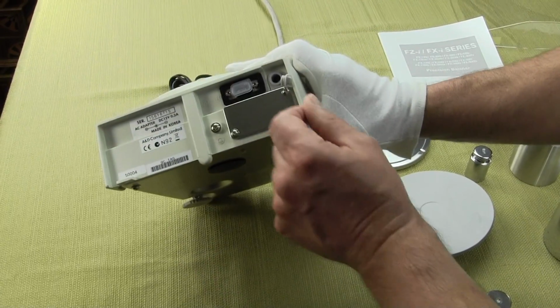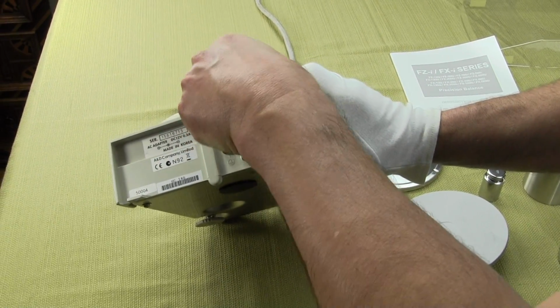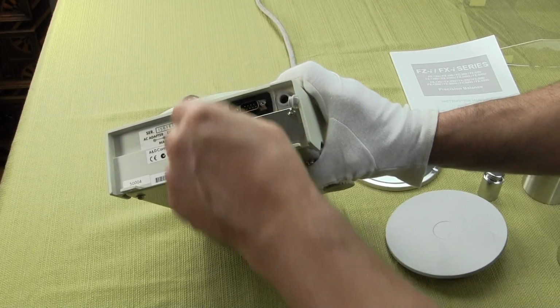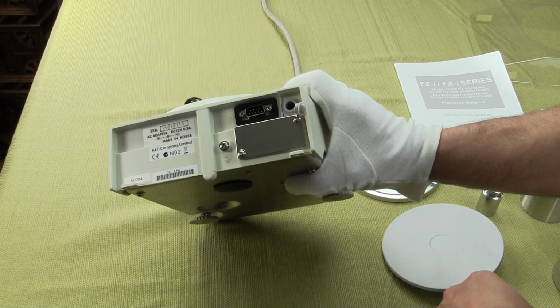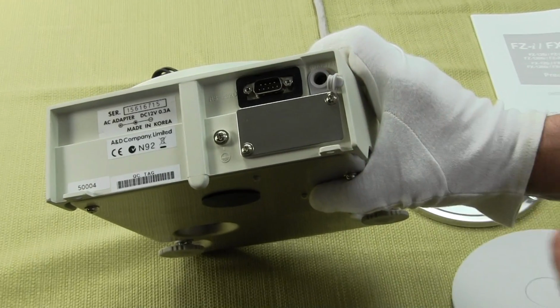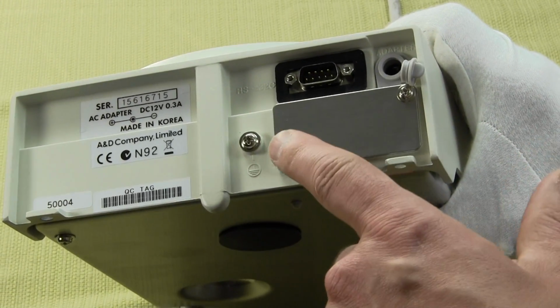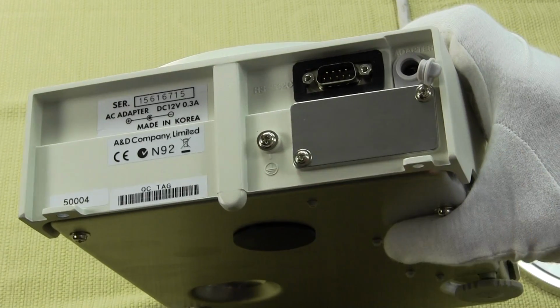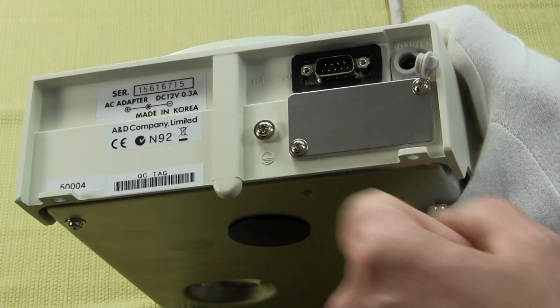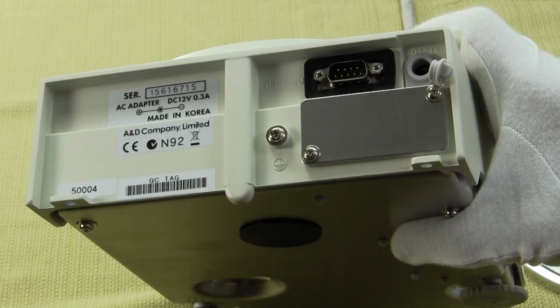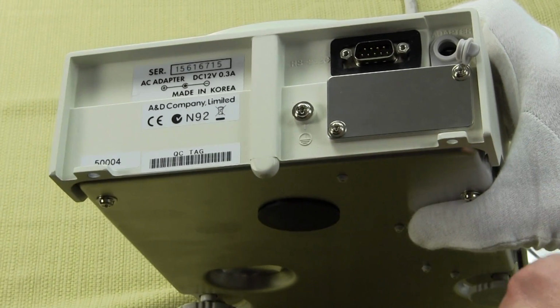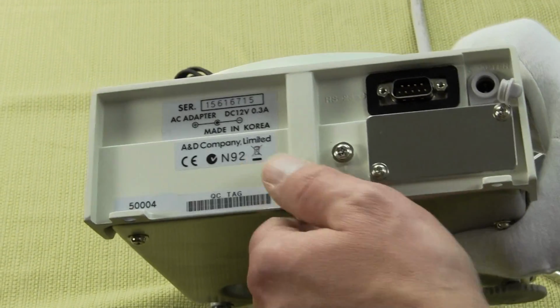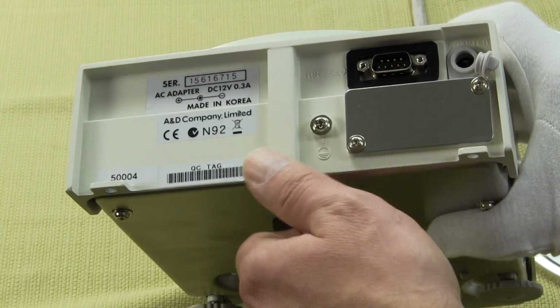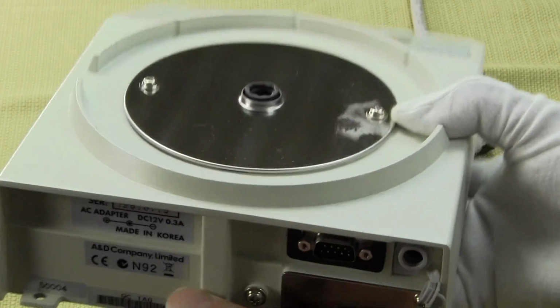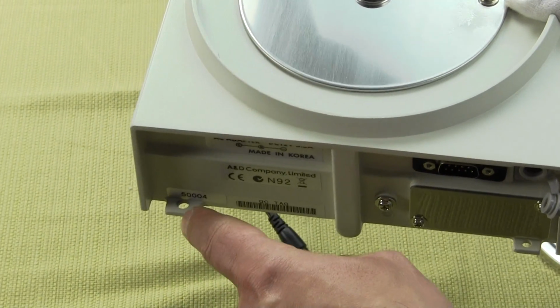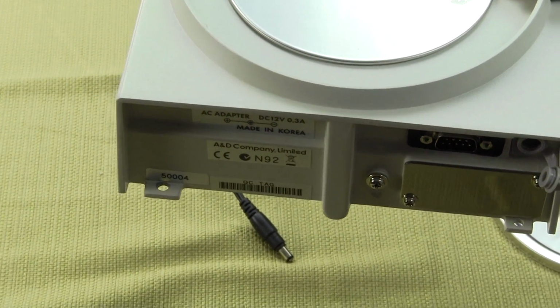On the rear of the balance, you'll see you have an RS-232 interface. So you have a 9-pin RS-232 interface. This would be used with a printer or if you're sending data to a PC. And then right under here, this is the port. And on this port here, if you open this up, you could put in either an Ethernet module or a USB module. So that's an accessory. This little screw here is for grounding your balance. And then at the very bottom, you have a little hook here that you put a cable through for locking down your balance.